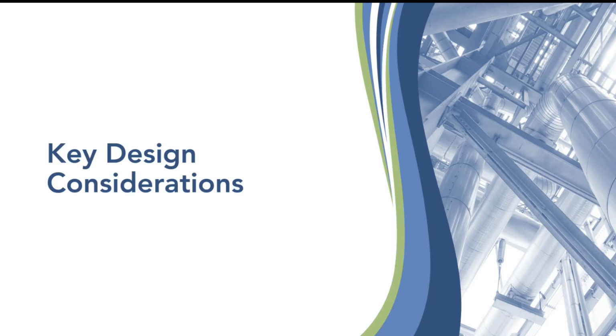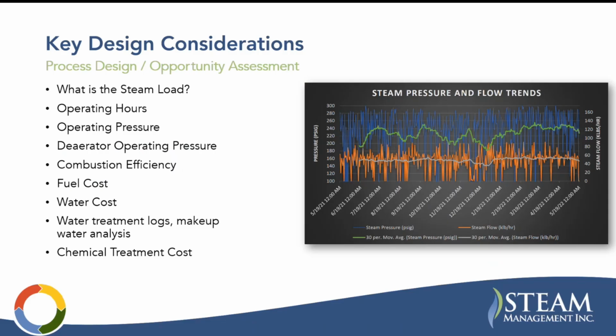Some key design considerations. Okay, you have to bear with me here. We're going to start getting into the weeds in a minute, but some things to think about, I'm saying process design, but also assessing the opportunity. So what is the steam load of the system? What are the operating hours, operating pressure, the deaerator operating pressure, combustion efficiency of the boiler? What are your utility costs, fuel costs, water costs, chemical treatment costs?